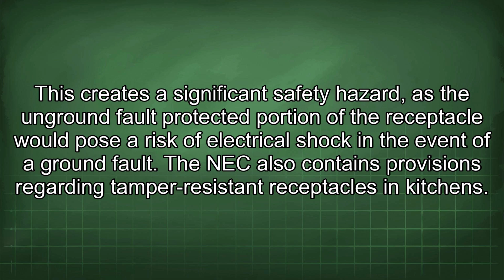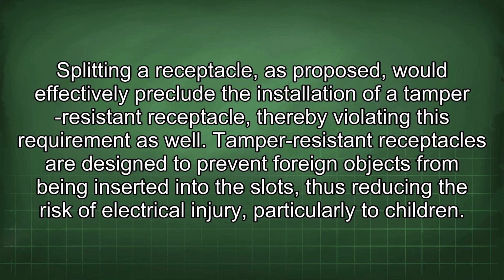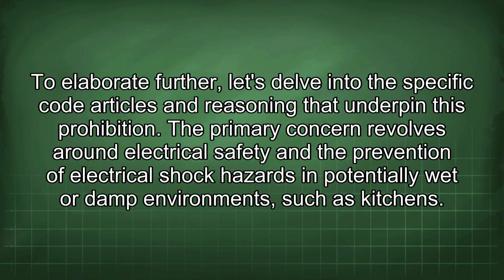The NEC also contains provisions regarding tamper-resistant receptacles in kitchens. Splitting a receptacle, as proposed, would effectively preclude the installation of a tamper-resistant receptacle, thereby violating this requirement as well. Tamper-resistant receptacles are designed to prevent foreign objects from being inserted into the slots, thus reducing the risk of electrical injury, particularly to children. To elaborate further, let's delve into the specific code articles and reasoning that underpin this prohibition.